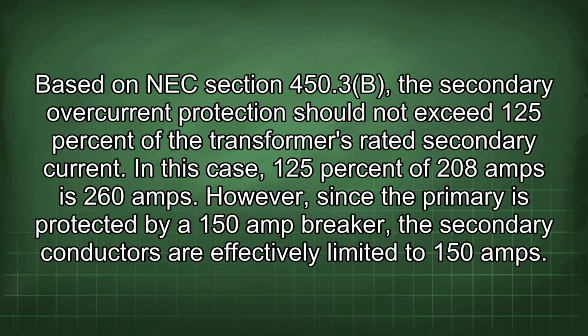Based on NEC section 450.3b, the secondary overcurrent protection should not exceed 125% of the transformer's rated secondary current. In this case, 125% of 208 amps is 260 amps. However, since the primary is protected by a 150 amp breaker, the secondary conductors are effectively limited to 150 amps.